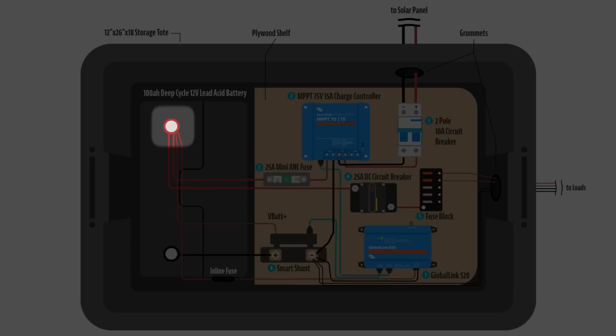This is an additional source of protection for the battery for any spikes that might come from that solar charge controller. From here, we come off the positive post of the battery through a 25 amp DC circuit breaker into a small fuse block or load center. This will allow us to isolate each item we want to connect and fuse them individually.